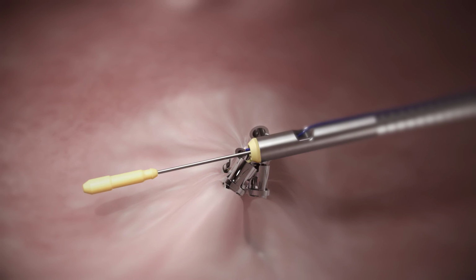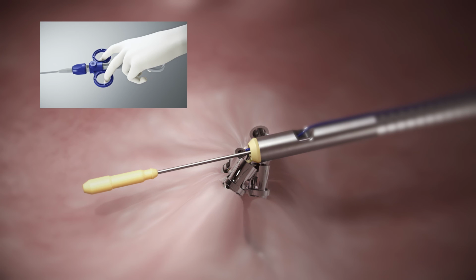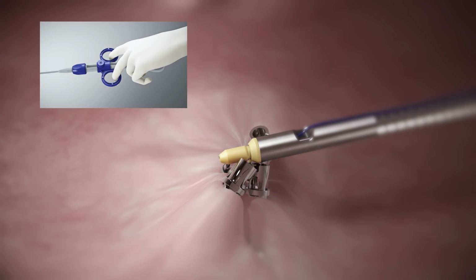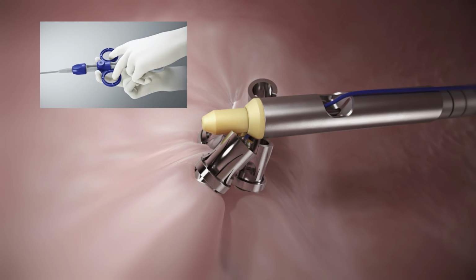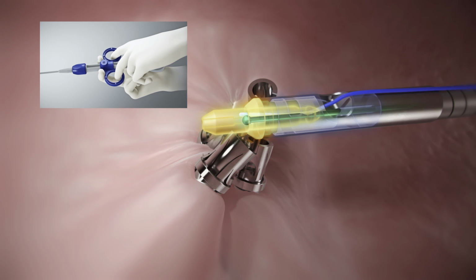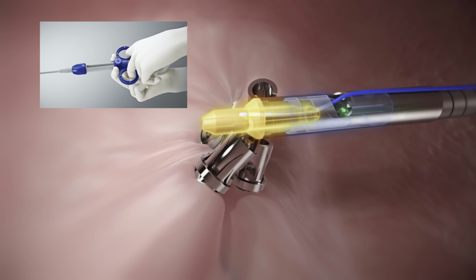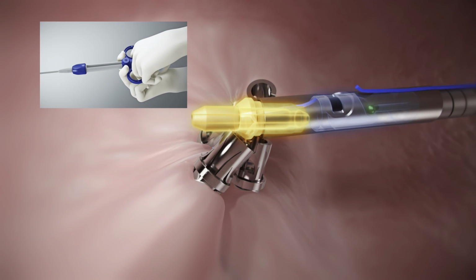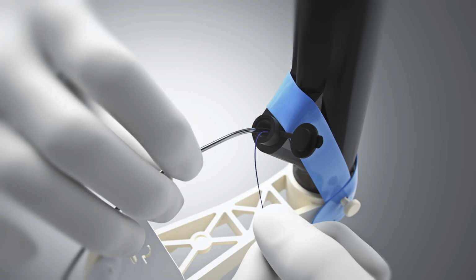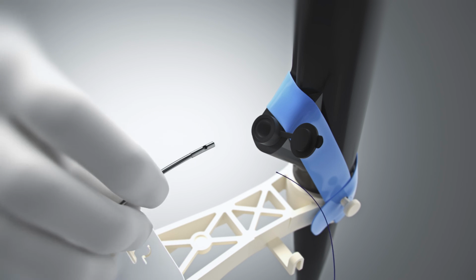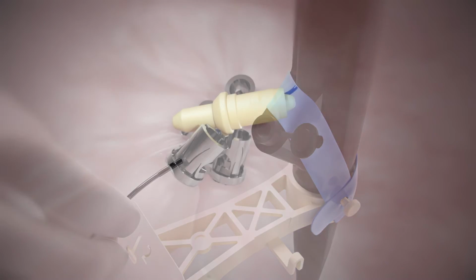Deploying the cinch is completed in 3 stages. Stage 1. Squeeze the cinch handle with one hand to pull the peak plug into the peak collar and lock the suture. Stage 2 of deploying the cinch will require 2 hands. Continue to squeeze the cinch handle to advance the beaded rod through the peak plug. Finally, continue to squeeze the handle to activate the suture cutter and release the peak collar and plug. Remove the cinch and remaining suture from the scope channel. Visually inspect final closure.